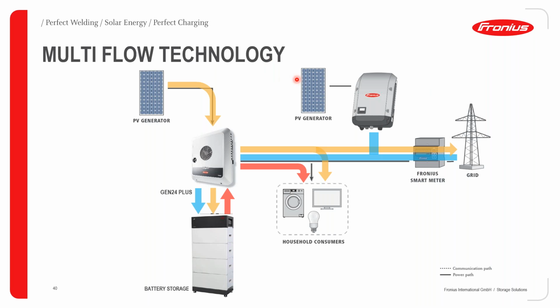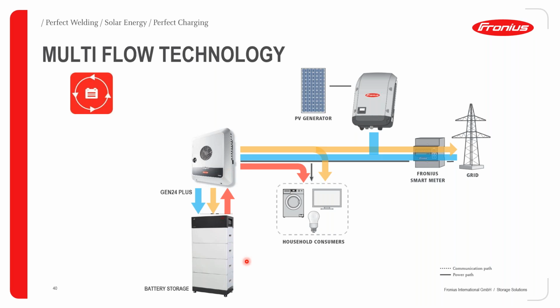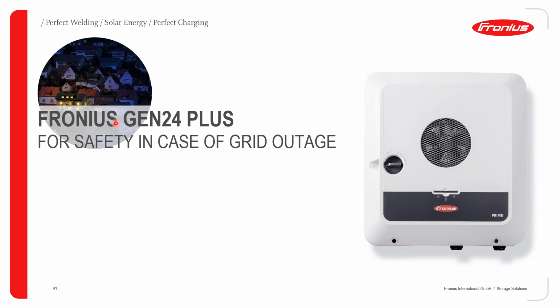Also, as another possibility with the multi-flow technology, if you have an existing PV array that is grid-tied or purely grid-tied installation, you can choose to retrofit the Gen 24 inverter in an AC coupled configuration to be able to utilize all the excess PV energy to be stored in the battery system. And this is what we are now calling, or referring to, as the multi-flow technology integrated in the Fronius Gen 24 inverters.